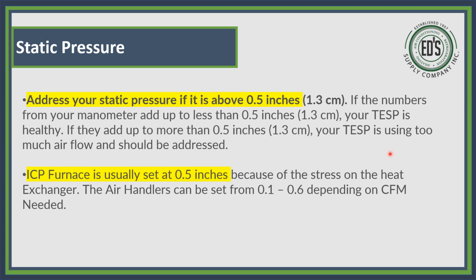Now, let's say you go to ICP. Furnaces are usually set so they do not want you over 0.50, because you put too much stress on the heat exchanger. And if you do not have everything done right, you'll have moisture in the heat exchanger. Moisture and static pressure will crack that heat exchanger, and you have the life all the way down to like 6 years. You'll be replacing a heat exchanger on something that should have lasted 20 years. And if you look at your install manual, ICP has a limited warranty on those heat exchangers. They can say we're not going to cover that because it's put in wrong. So you need to really look at your install manual.